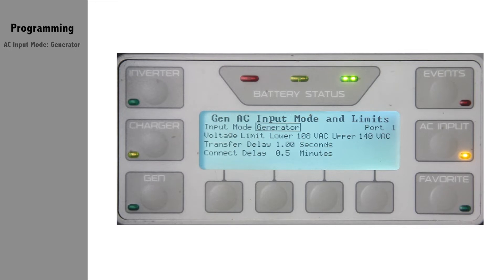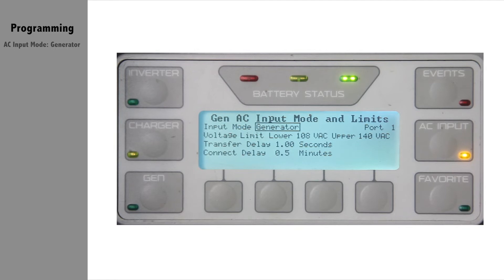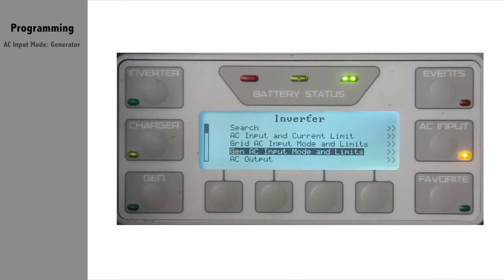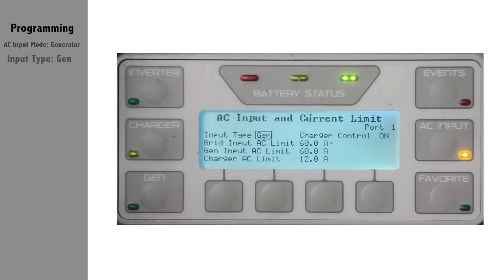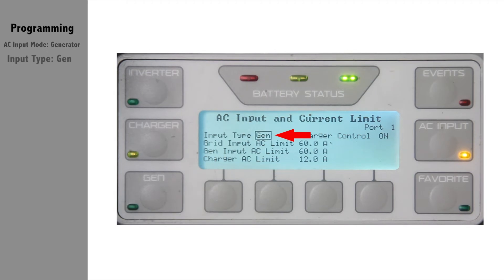While we are still here, also make sure you have your input priority or type set to gen. Radian and FXR inverters have two input types with separate programming criteria. For this purpose, we want generator input to be active. Press up once, then scroll up to AC input and current limit. Check your input priority or type to be set to gen.